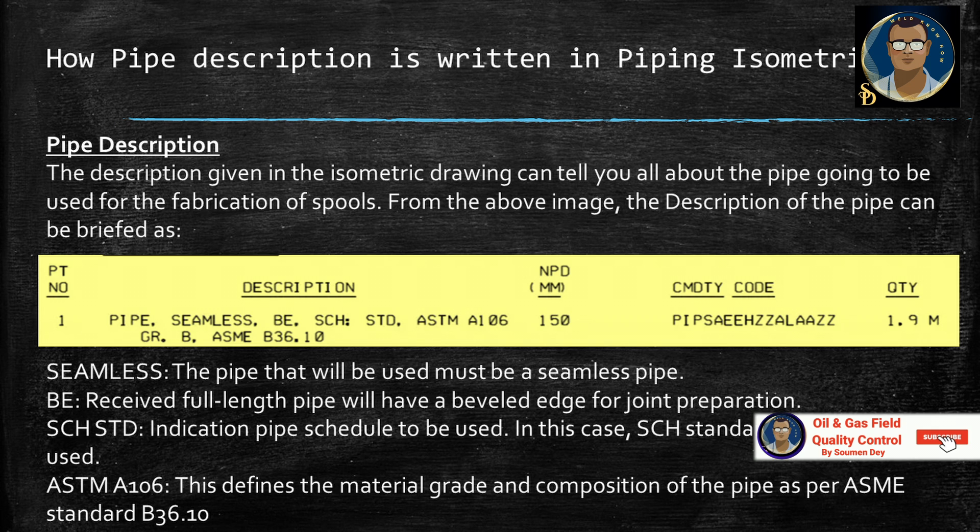From the above image, the description of the pipe can be briefed as: Pipe, seamless, BE, schedule STD, ASTM A106 grade B, ASME B36.10, NPD 150mm, and quantity is 1.9 meter.